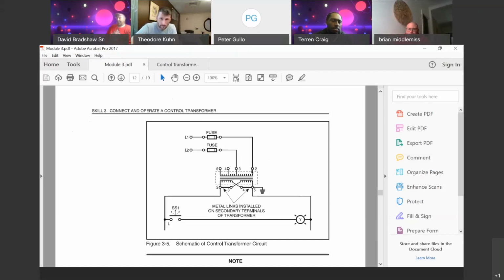The other thing I want you guys to remember, you see this 2 on the primary side with 3? Don't misconstrue that 2 with the 2 on the secondary side, two different type of 2s. I've seen people wire that by mistake and think it was the 2 on the primary, and we had to check and tell them no, you could have blown some fuses there, so don't get them misconstrued.